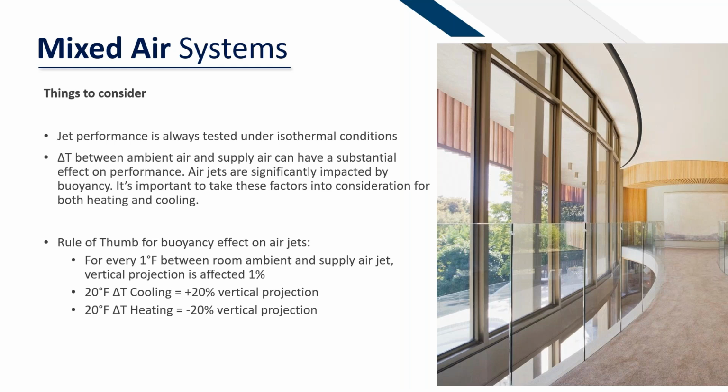So just taking that into account, when I'm sizing something like this, I would look at the heating side first. Make sure you're good on the heating side, and you can back into your cooling side and usually be good in most cases. So just something to keep in mind when you're factoring these in and sizing these up.